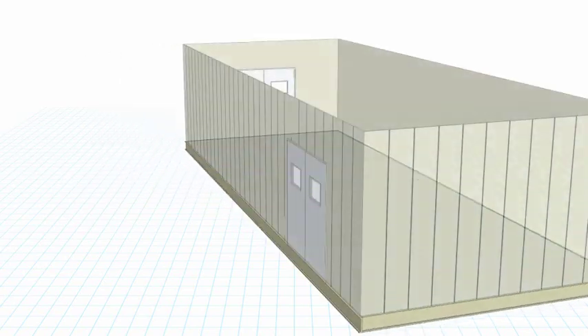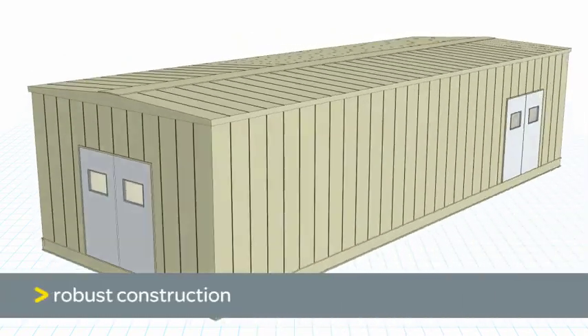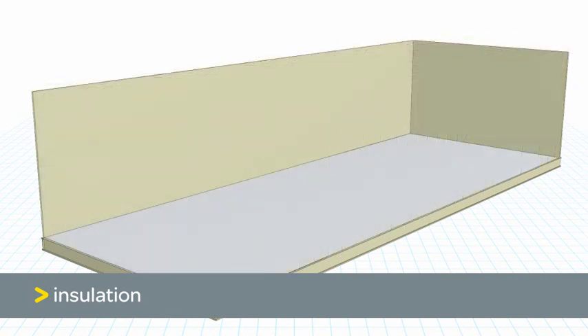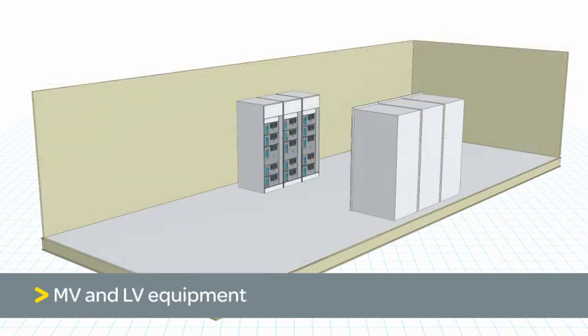The container is manufactured using interlocking galvanized steel wall and roof panels, welded steel supports and insulation as required by the environmental conditions. Inside is the necessary switchgear, containing medium and low voltage distribution and control equipment, as well as motor control centers, variable speed drives, intelligent energy meters and dry transformers. It also contains UPSs, batteries and any required HVAC, fire and lighting equipment.